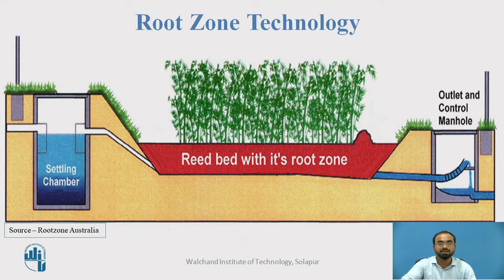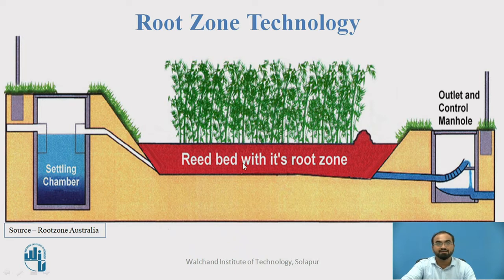In the picture, you can see the wastewater which is collected in the settling chamber is fed as an inlet into the root zone technology system, in which the red part has a lot of gravel on which reed bed plants have been implanted and grown. Their roots will automatically percolate inside the gravel, providing a large surface area so that microorganisms near the roots and adhered to the gravel will take out whatever organic matter is flowing through the water.